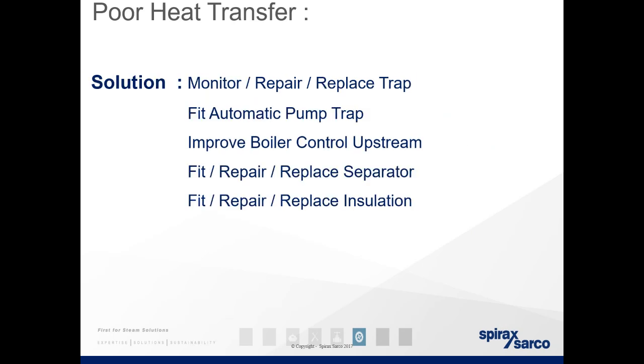Solutions: monitor, repair or replace steam traps. Fit automatic pump traps in the case of stall. This is particularly relevant when you have the inability to create a header pressure. So for instance, if you have a heating unit near the roof space, by creating a header, by dropping the trap close to the floor, you limit the ability of stall. This could be a heat exchanger system doing the same sort of thing.